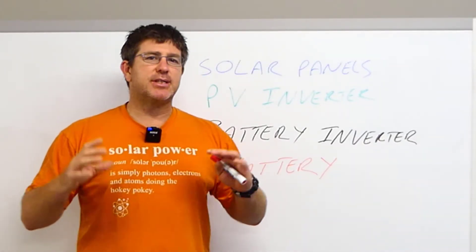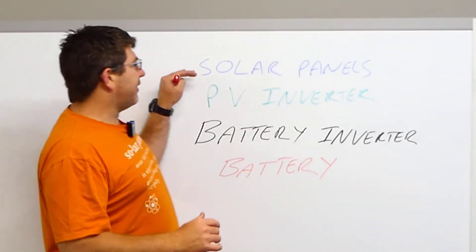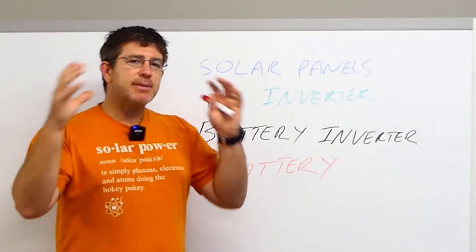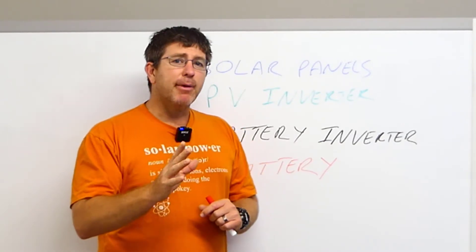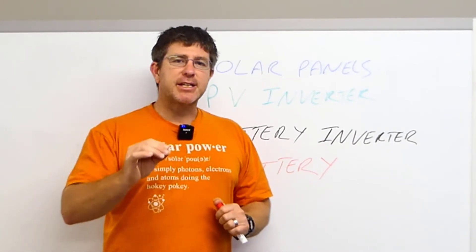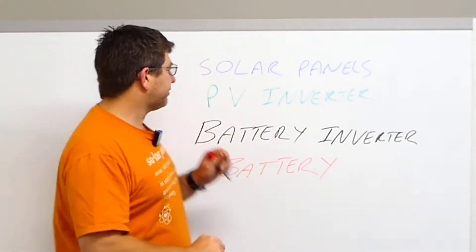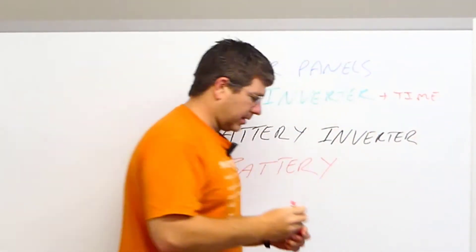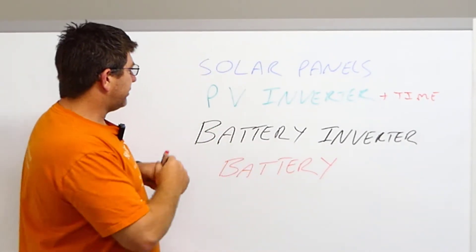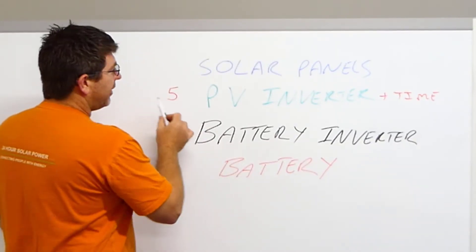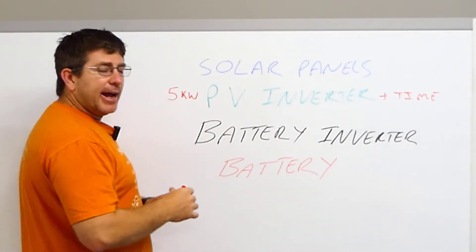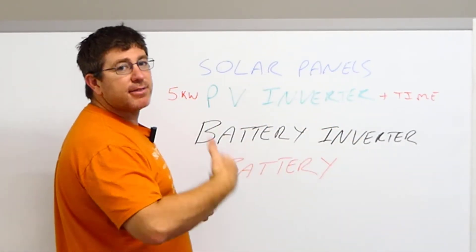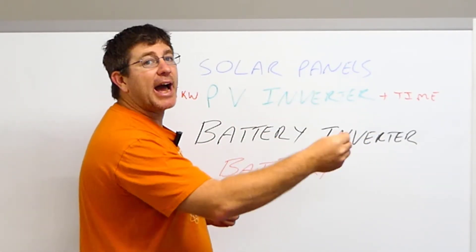Let's jump back to the whiteboard and see how this relates to solar. Everyone talks about 6.6 kilowatts of panels. In theory, if those 6.6 kilowatts of panels were put on a 6 or 7 kilowatt inverter, that's the most energy they could produce at any one moment. If you've got a 5 kilowatt PV inverter, that's the maximum peak energy you can produce at any one time. When you add time to the PV inverter, that's when you get the kilowatt hour. For example, a 5 kilowatt PV inverter at peak production can do 5 kilowatts. Add 5 sun hours — 5 times 5 is 25 — so you get 25 kilowatt hours.